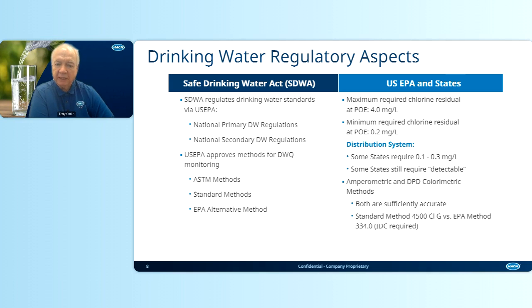Maximum required chlorine residual at the point of entry is 4.0 milligrams per liter. That's actually an annual running average, so maybe a little higher in the summer and a little lower in the winter. The minimum is 0.2 milligrams per liter at point of entry. In distribution systems, it varies with states. Some require 0.1 to 0.3 milligrams per liter. Other states still require just a detectable amount.